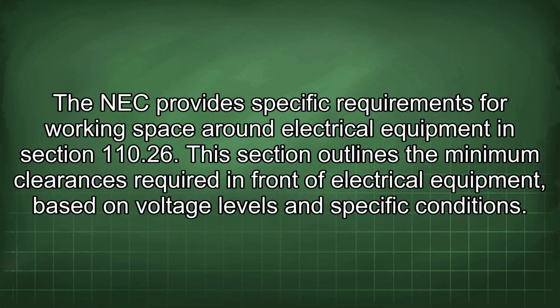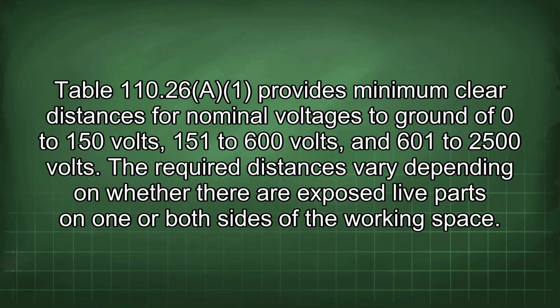The NEC provides specific requirements for working space around electrical equipment in Section 110.26. This section outlines the minimum clearances required in front of electrical equipment based on voltage levels and specific conditions. Table 110.26(A) provides minimum clear distances for nominal voltages to ground of 0 to 150 volts, 151 to 600 volts, and 601 to 2500 volts. The required distances vary depending on whether there are exposed live parts on one or both sides of the working space.